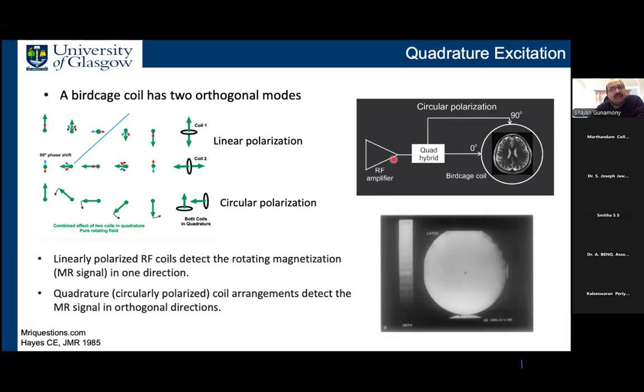The output from this amplifier is then fed to a quadrature hybrid. The function of the quadrature hybrid circuit is that it splits the power into 2 outputs, which is minus 3 dB. But the 2 outputs will have a phase difference of 90 degrees. So these 2 outputs are then given to a birdcage coil at 90 degrees apart. So then we set up this kind of a circular polarization and we get a homogeneous image like this.